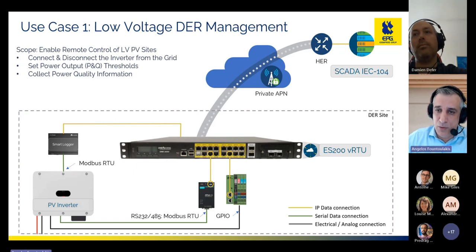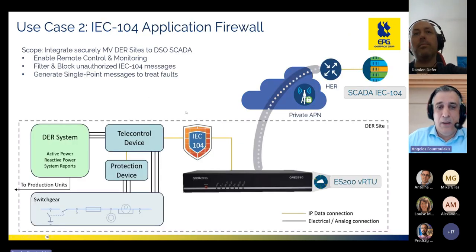That's a simple use case: remote control of a remote site. A second case is a medium voltage installation where the customer has invested in their own SCADA system. We don't want to allow that SCADA system to send commands to our central distribution or SCADA system, so we filter and allow only specific commands on the IEC 104 protocol using our software, again running on an Equinox device with Nuvla Edge. We create an application firewall to establish a security separation between the private investor side and this critical infrastructure command and control system. We can also handle single point information on various protocols in order to treat faults.